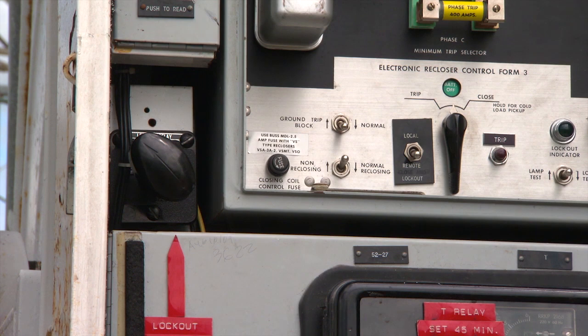The timing delay prevents the 86 relay from tripping the mobile in the event of a reclose operation on the 115 kV circuit. Once the test is complete, place the local remote switch back to the local position.